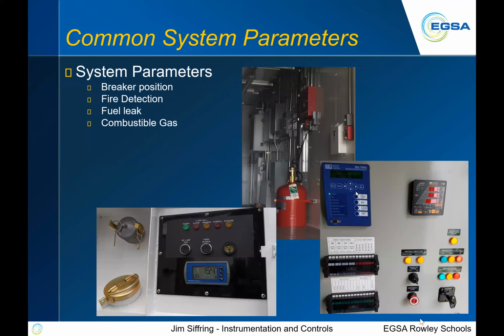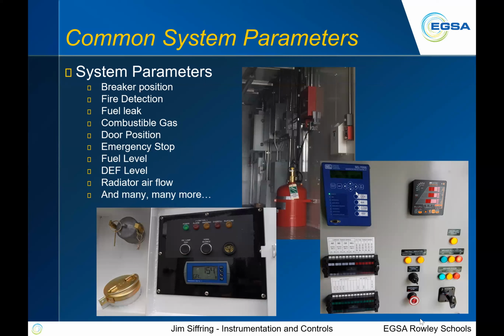Fire detection, obviously that's a very important thing. Fuel leaks, another very important thing. Combustible gas: is there a leak in the natural gas system or something? What are the door positions, things like that? What's the position of the emergency stop switch? How about fuel levels, DEF levels, radiator airflow? Is the fan belt broken? Things like that. Many, many more things that we want to look at.